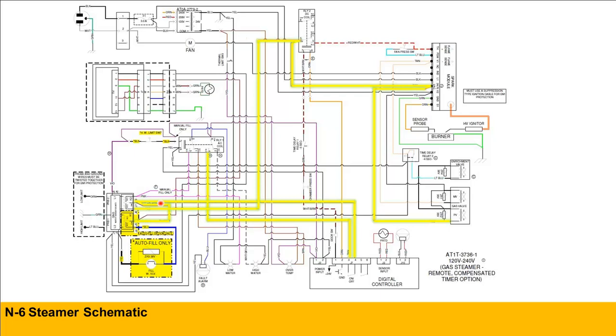So if we have 24 volts AC, and we have static pressure because we know we have a manometer on, but we don't have a light in the module. Now, at this point, ignition hasn't been triggered. So we're keeping this one out so we can test it here. But if we have power at the pin, and as long as there's no break in the wire, we're going to have power here, so I'd normally leave that alone. I know I have static pressure, so I'm not going to touch that. But once again, I do have an AC input basically energizing the module.